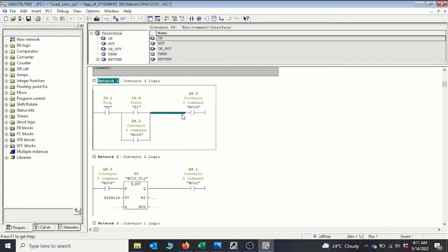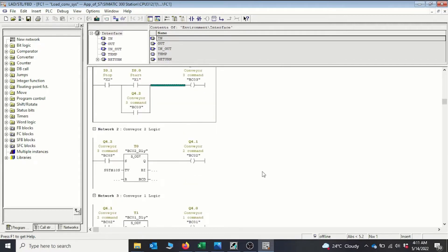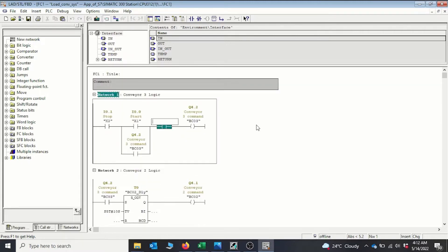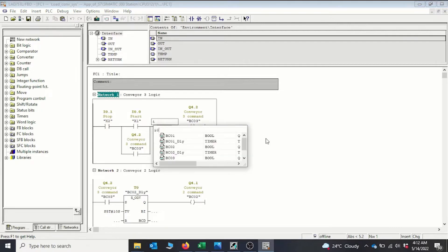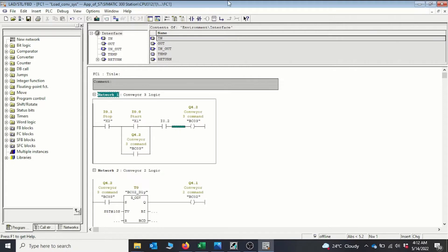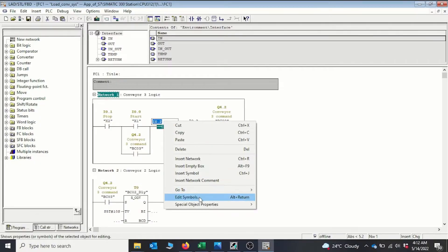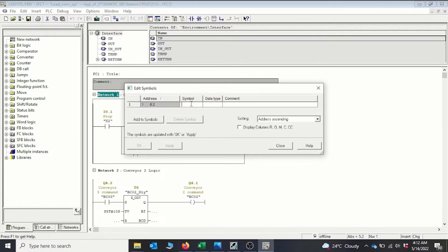Looking at this logic, if we introduce the emergency pull rope on this particular line, we should be able to stop all the conveyors whenever there are emergencies. I will introduce a normally open contact here, since the emergency pull rope switches on field are normally closed. This is the input to receive the emergency pull rope signal. Looking at the inputs we've used — I0.0, I0.1, I0.2 — we can use I0.2. The next one will be our emergency stop push button at I0.3. So we can give them symbolic names: Edit Symbol — this is going to be our EMG emergency stop input.